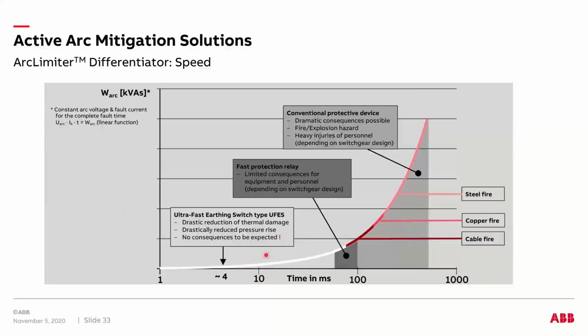So here is a similar curve that I showed in the previous few slides. For an arc flash relay, we are somewhere in the range of 80 to 100 milliseconds. And for a conventional protective device, especially for an arc flash event, we are in a highly explosive range where you could have heavy injuries to the personnel as well as to the equipment. And here is the reaction time by using a UFES or a high-speed grounding switch, where you are completely eliminating an arcing fault in about 4 to 5 milliseconds right here.